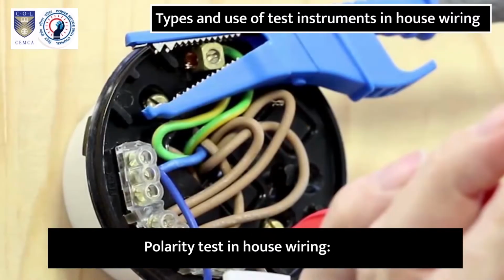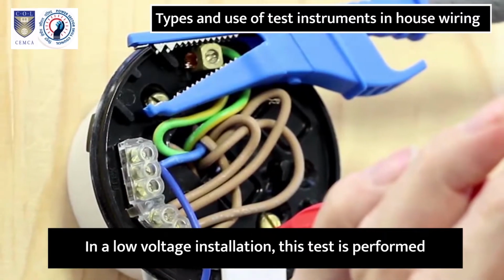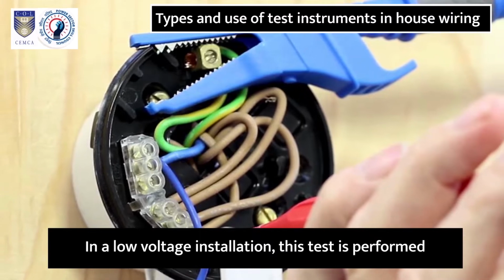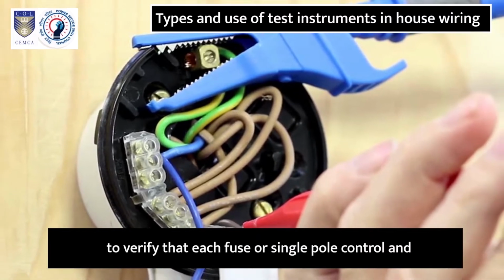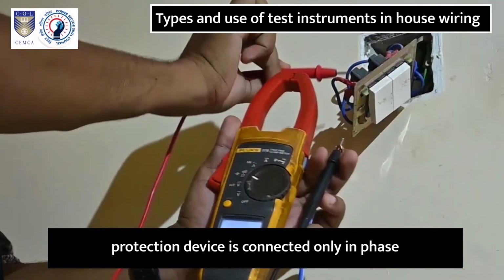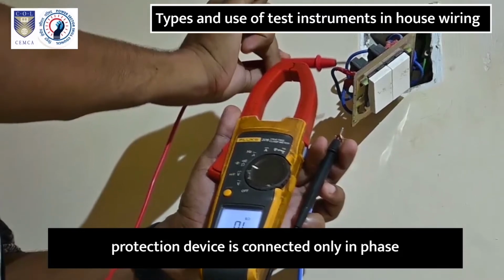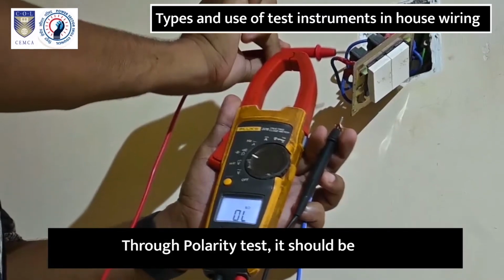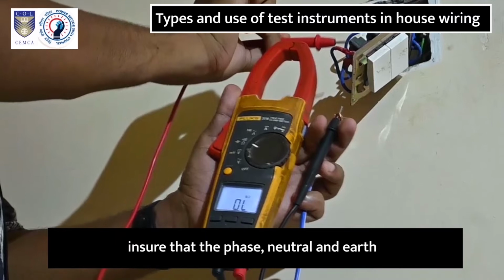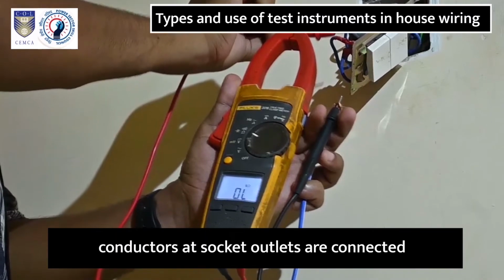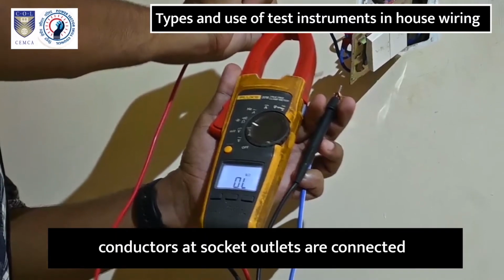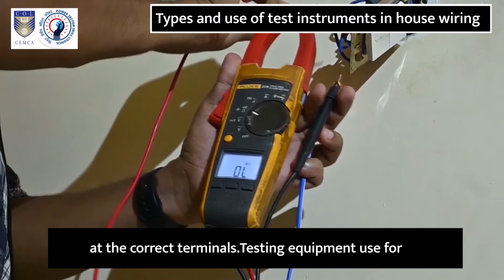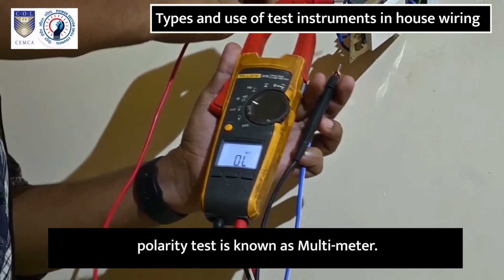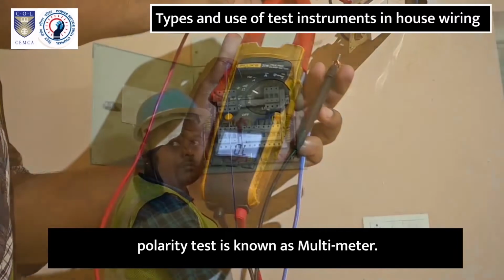Polarity test in house wiring. In a low voltage installation, this test is performed to verify that each fuse or single pole control and protection device is connected only in phase wire throughout the installation. Through polarity test, it should be ensured that the phase, neutral and earth conductors at socket outlets are connected at the correct terminals. Testing equipment used for polarity test is known as multimeter.